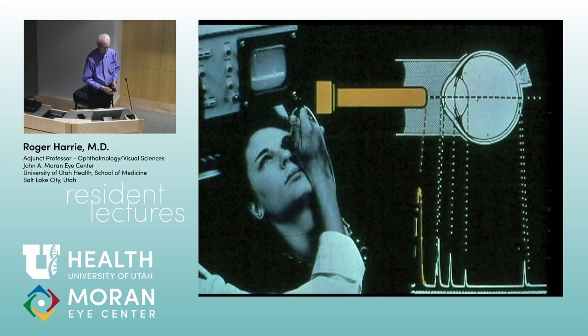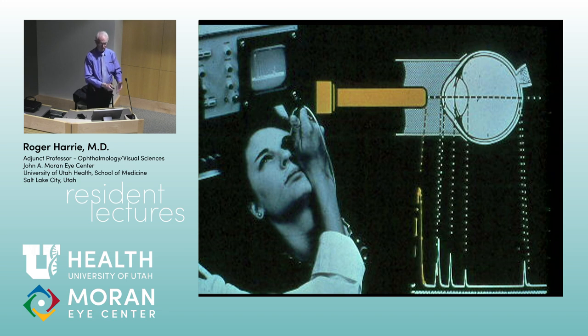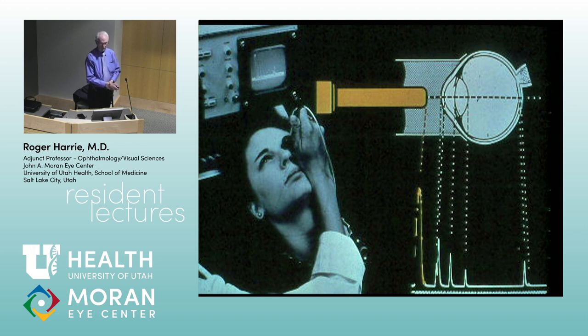For biometric axial length, we use immersion techniques so we can see the front structures of the eye. If you put the probe right against the cornea you lose information — you can't see the cornea, anterior chamber, or anterior lens. With an immersion shell, you get the probe spike, then cornea, anterior chamber, anterior lens, posterior lens, vitreous, and retina — you can measure front to back with electronic calipers. About 20% of the time, techs have to do immersion ultrasound instead of IOL Master.